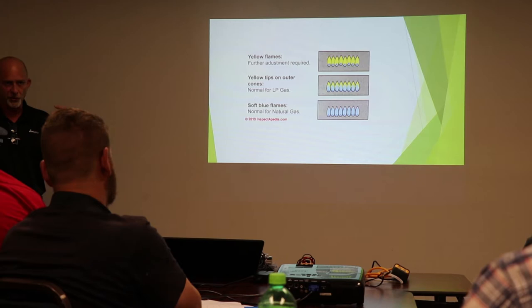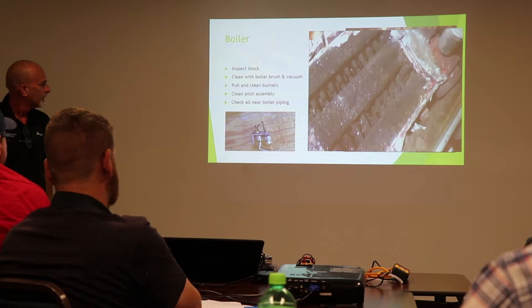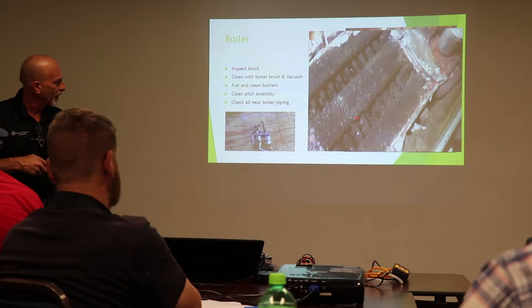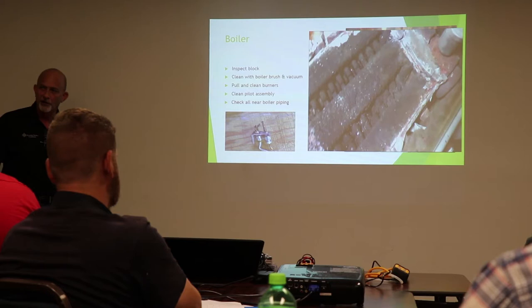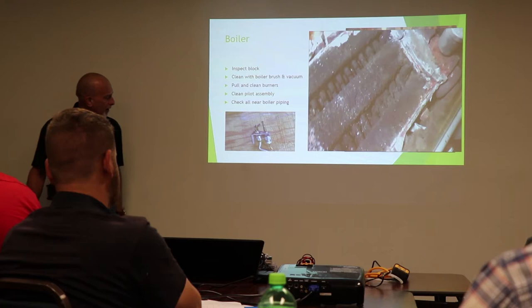Boilers. Minimally, we want to take off our vent pipe and look inside down a boiler. What do we got going on here? We're all suited up, right? That boiler going to work good? No. Of course, we want to pull our burners out, pull out our pilot assembly. Got to make sure that's all clean. Anybody ever have to kind of clean a boiler that looked like that before?